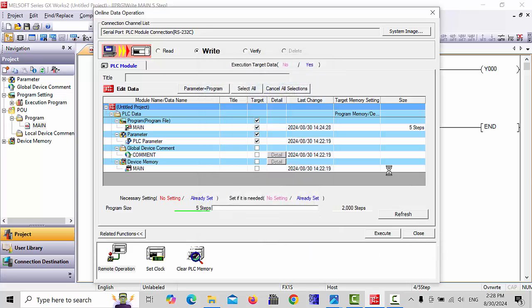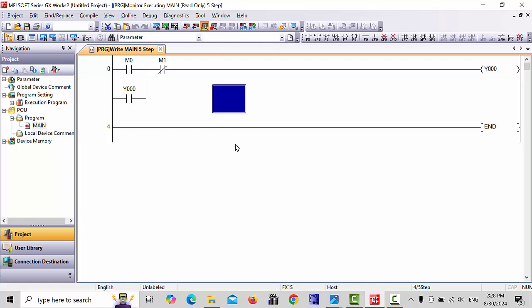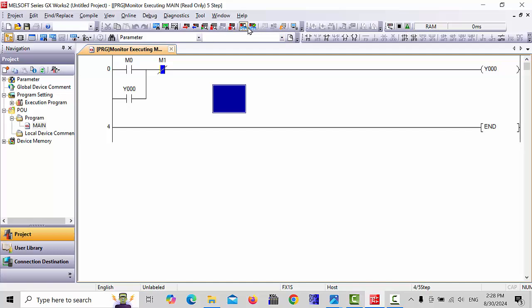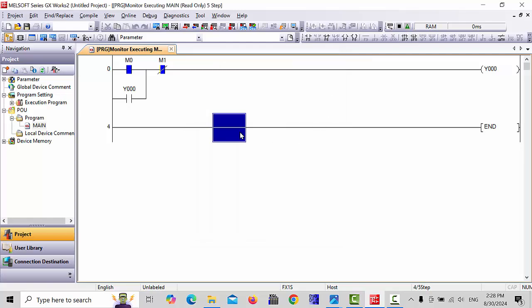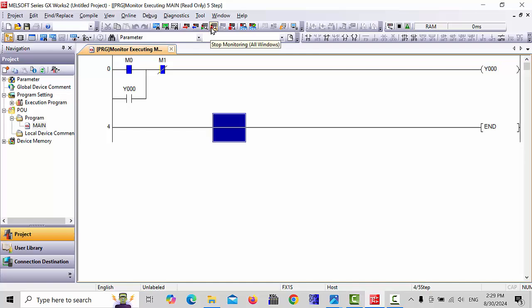After that, you have to go to Monitoring, Start Monitoring All Windows. Now your monitoring is started. First, this is in stop condition. Stop monitoring. Go to connection channel COM4, PLC module, and set it to Run. When you make it Run condition, it completes. Click OK. Close the dialog. Your PLC is now running.